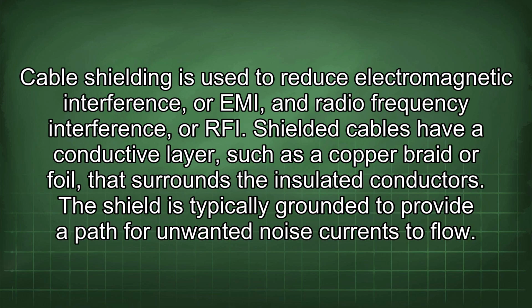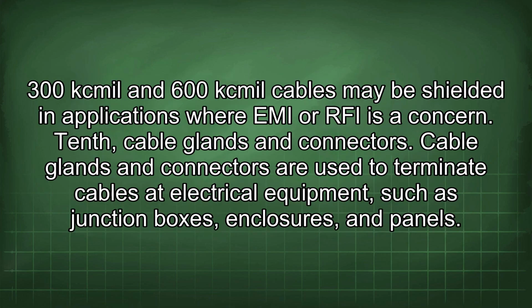Cable shielding is used to reduce electromagnetic interference, or EMI, and radio frequency interference, or RFI. Shielded cables have a conductive layer, such as a copper braid or foil, that surrounds the insulated conductors. The shield is typically grounded to provide a path for unwanted noise currents to flow. 300kcmil and 600kcmil cables may be shielded in applications where EMI or RFI is a concern.